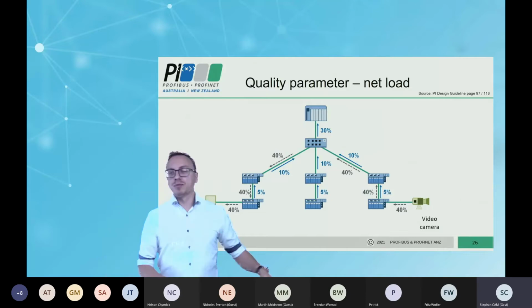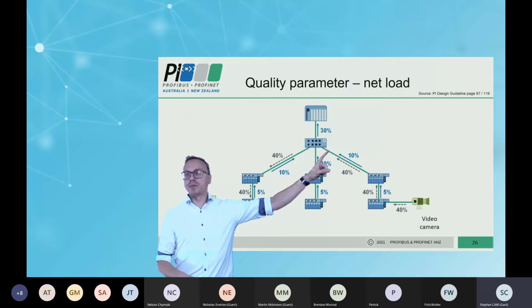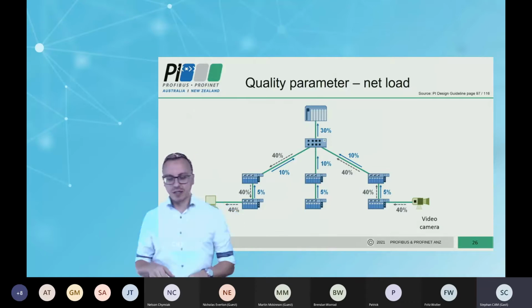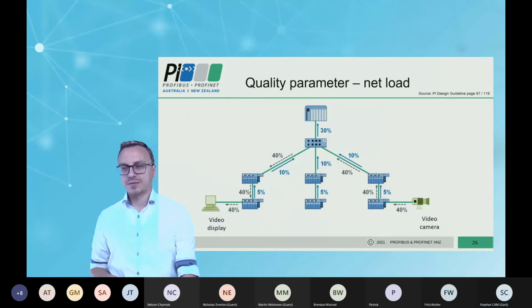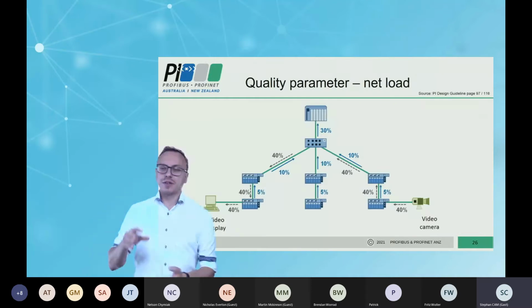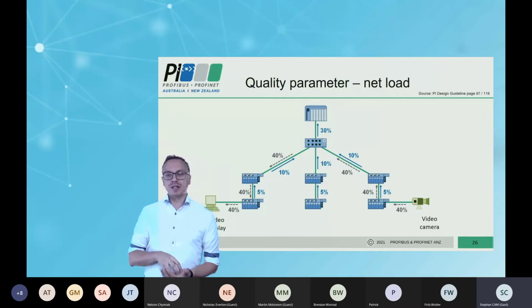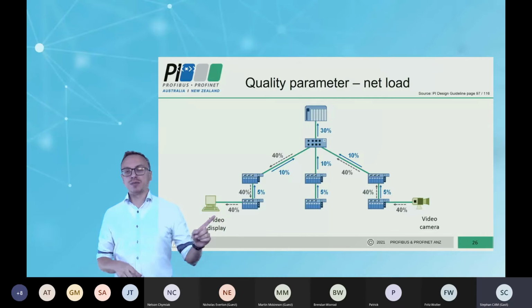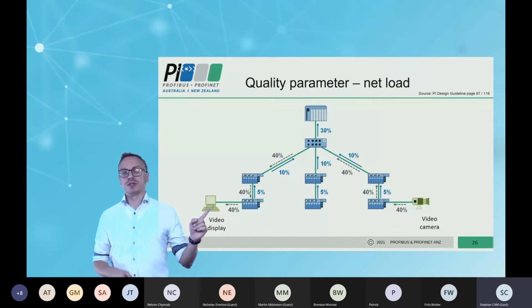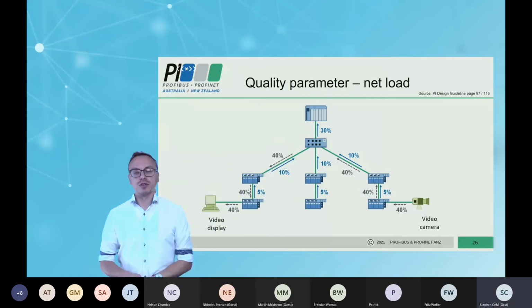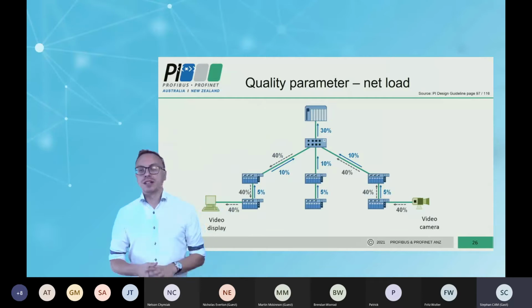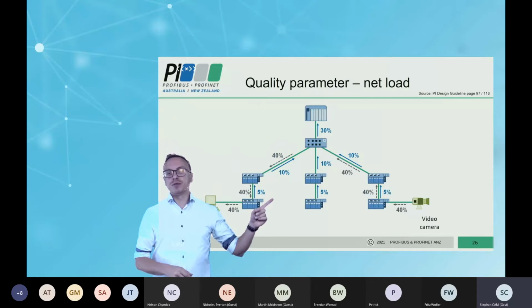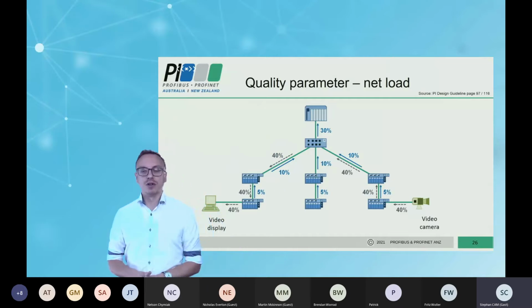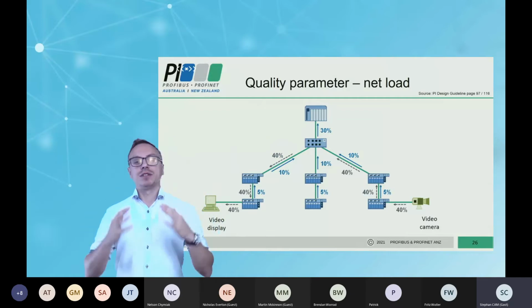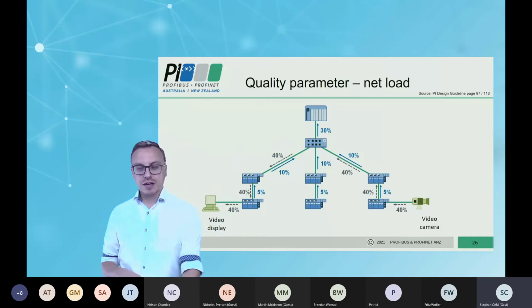In the slides, I put the PI design guideline every time so that you can also read it directly from the guideline itself, if you would like. So maybe some additional words on the net load. You can decrease the net load if you don't connect TCP/IP devices directly in your network. The recommendation is normally to connect TCP/IP devices directly to a switch, because a switch can forward frames to the right port. And the other thing is, if you want to decrease the net load of your I/O devices, you have to reconfigure your update time, because if you increase your update time, you will decrease the net load of your cyclical communication.